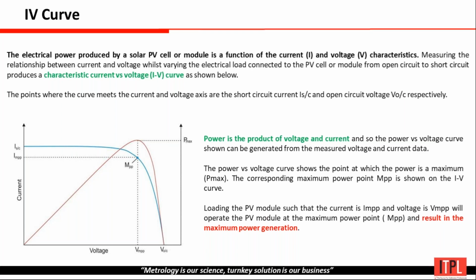The equipment itself has an inbuilt load. So whenever we connect with the MC4 or MC3 connector, whichever connector it is, when we start the testing, the inbuilt load in the equipment will start working, and it will short circuit the solar panel and connectors, giving us the immediate values of all the parameters from the solar panel, like open circuit voltage, short circuit current, voltage at maximum power point, current at maximum power point, peak wattage, and fill factor.